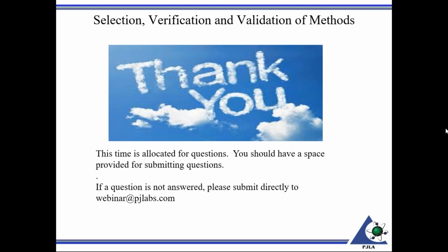Do we need to have a certificate of calibration from a third party before we can officially use the equipment, the balance? I'm assuming you're referring to your calibration report. Again, the standard does not address that. I would say you may not be able to get the calibration report directly. Then you probably want to get assurance that when the calibrator leaves, it's within tolerance.